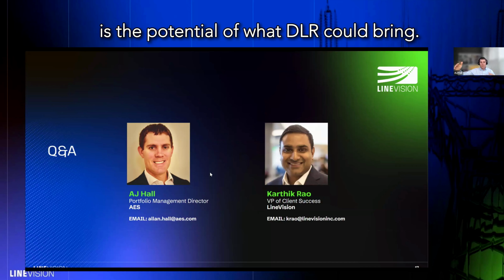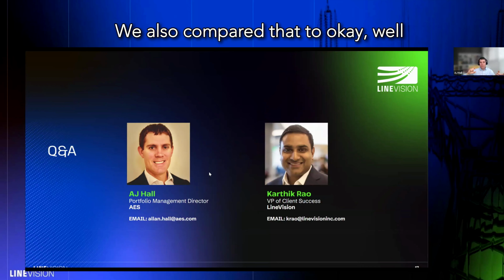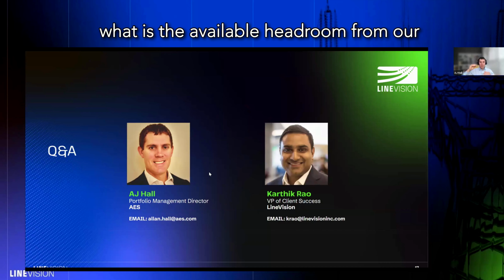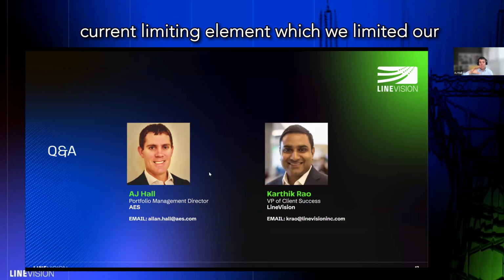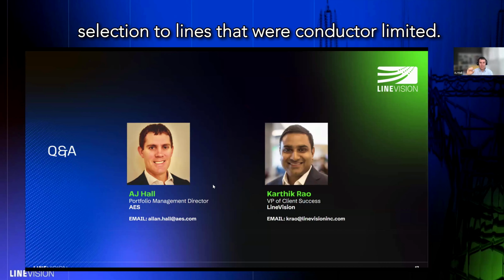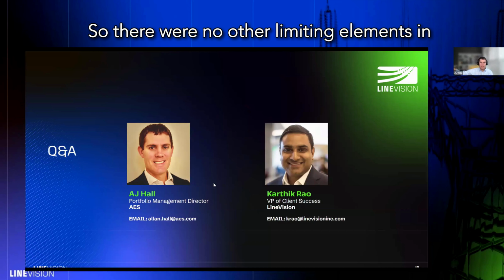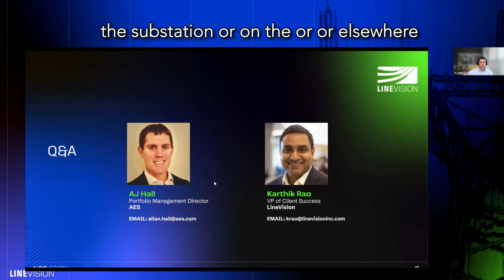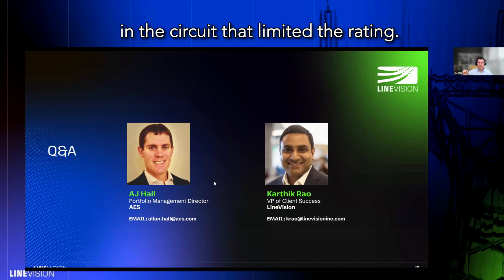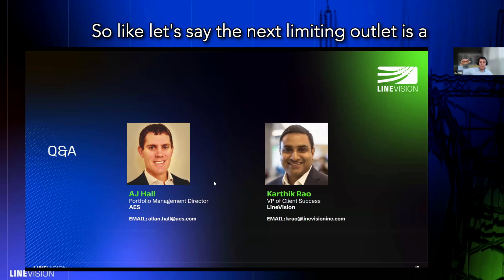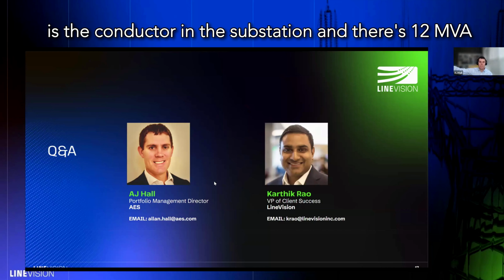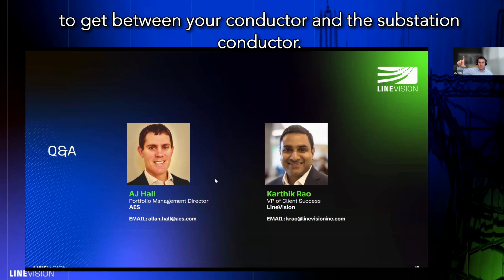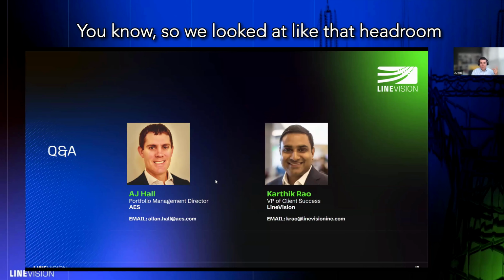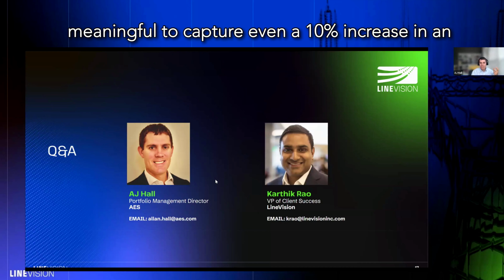After that line selection process, once we received the line profiling studies, we could say this is the potential of what DLR could bring. We also compared that to what available headroom exists from our current limiting element, since we limited our selection to lines that were conductor limited, meaning there were no other limiting elements in the substation or elsewhere in the circuit. Then we looked at the next limiting element, say the conductor in the substation, and there might be 12 MVA between your conductor and the substation conductor. So we looked at that headroom and what percent of it would be meaningful to capture.